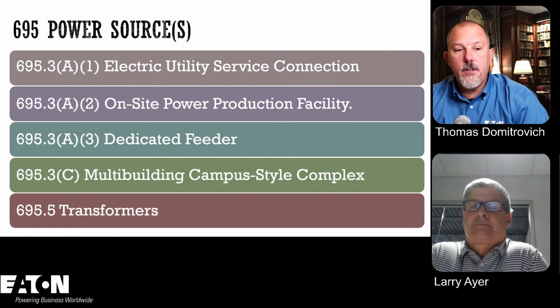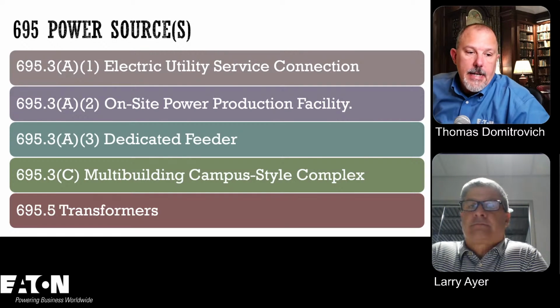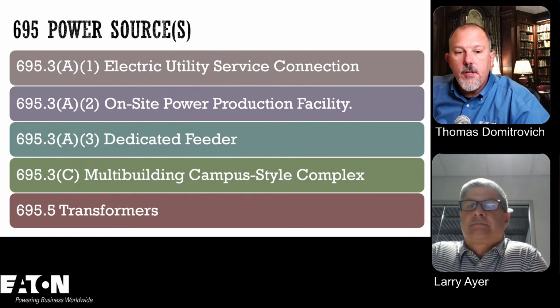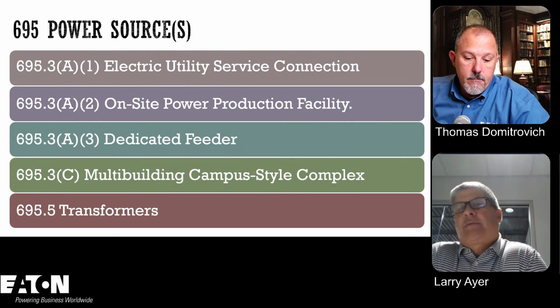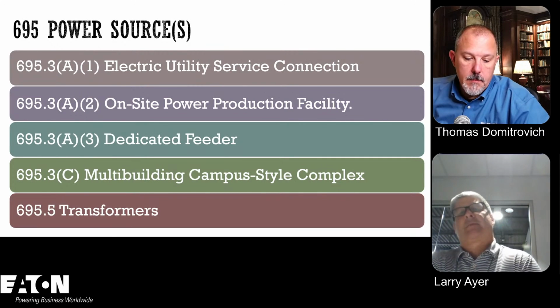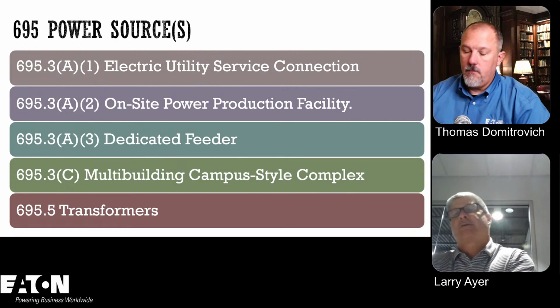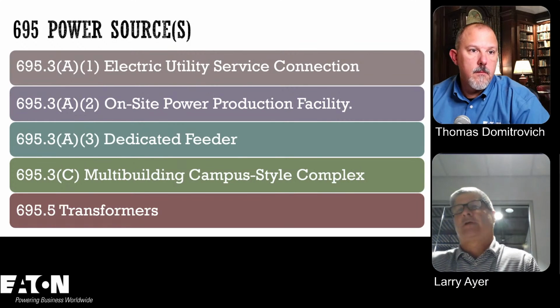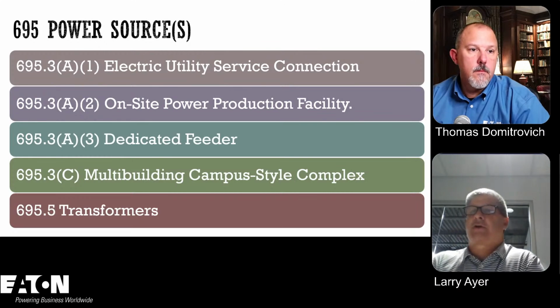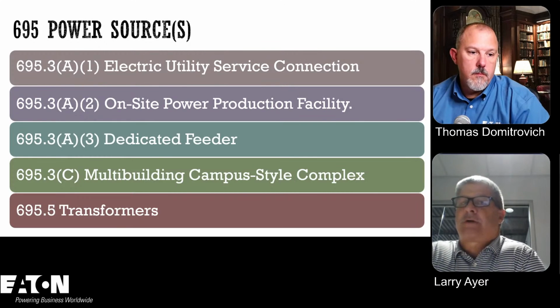Okay, now Jeff Facteau is on the line. Thanks for joining us, Jeff. He says if the service is 13.2 and all the utility offers, and I guess that's all the utility offers, not campus style application, does the service or the fire pump also have to be 13.2? He says we passively mentioned a transformer. I've dealt with a couple of these, and in my experience, most of these you're not going to put in a 13.2 fire pump, so you're going to need to put some type of step down transformer.